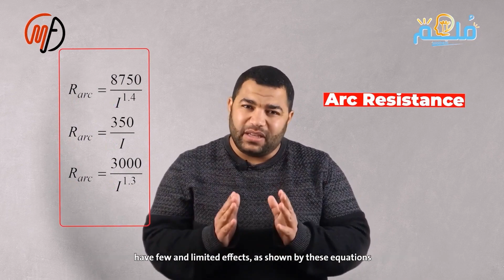The third factor affecting the value of the fault current is the strength of the power supply. The first factor is the location of the fault, and the second factor is the value of the fault resistance. The third factor is the strength of the power supply, which is expressed by the low impedance of this source. The lower the impedance of this source, the stronger the source is, and it has the capacity to feed the fault.